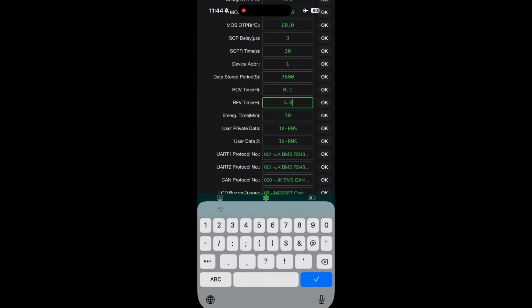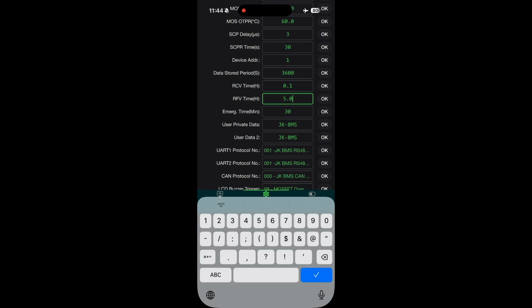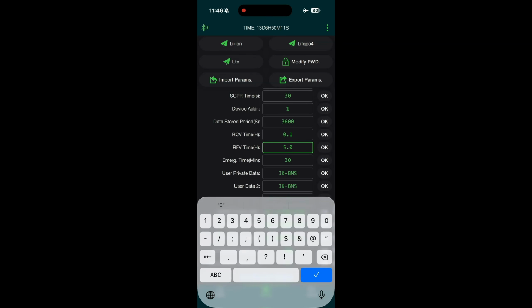Next one is the requested float voltage. Okay, so this is how long the BMS will hold the battery at the highest absorption voltage before it switches to the lower float voltage. Okay, so it's currently set to 5, which, again, this is in hours, right? So I'm going to change this to 0.5.